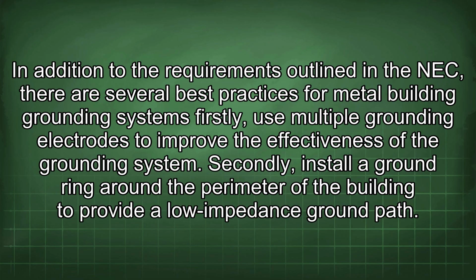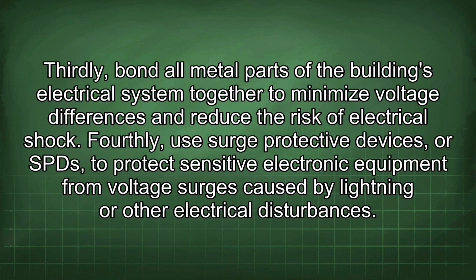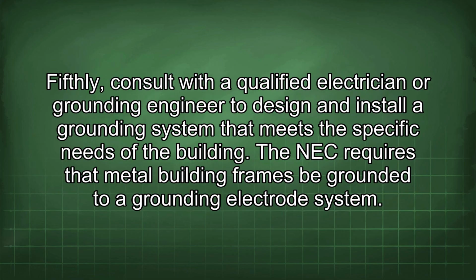In addition to the requirements outlined in the NEC, there are several best practices for metal building grounding systems. Firstly, use multiple grounding electrodes to improve the effectiveness of the grounding system. Secondly, install a ground ring around the perimeter of the building to provide a low impedance ground path. Thirdly, bond all metal parts of the building's electrical system together to minimize voltage differences and reduce the risk of electrical shock. Fourthly, use surge protective devices, or SPDs, to protect sensitive electronic equipment from voltage surges caused by lightning or other electrical disturbances. Fifthly, consult with a qualified electrician or grounding engineer to design and install a grounding system that meets the specific needs of the building.